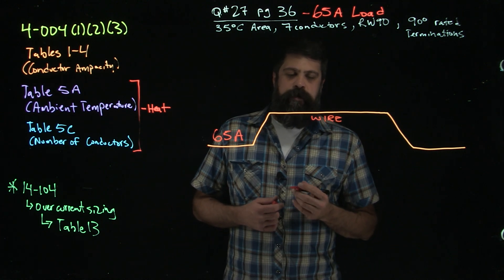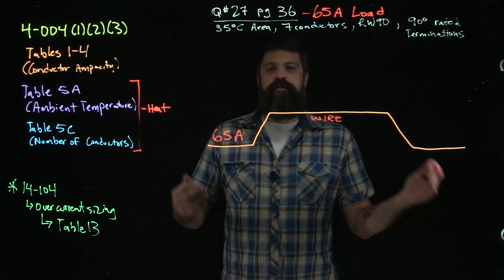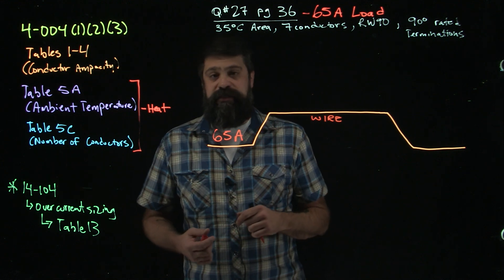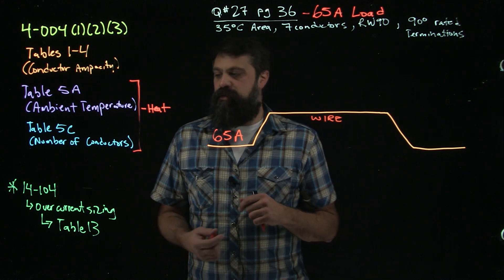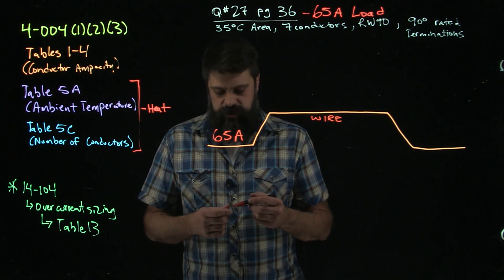This is where we find our wire. In order to figure out what wire size we need, we have to take into account tables 5A and 5C. That tells us based on the heat, based on the number of conductors, how do I start to derate this thing.